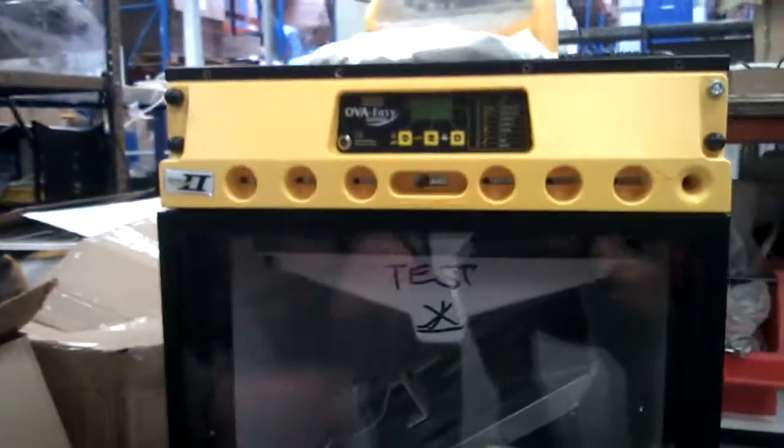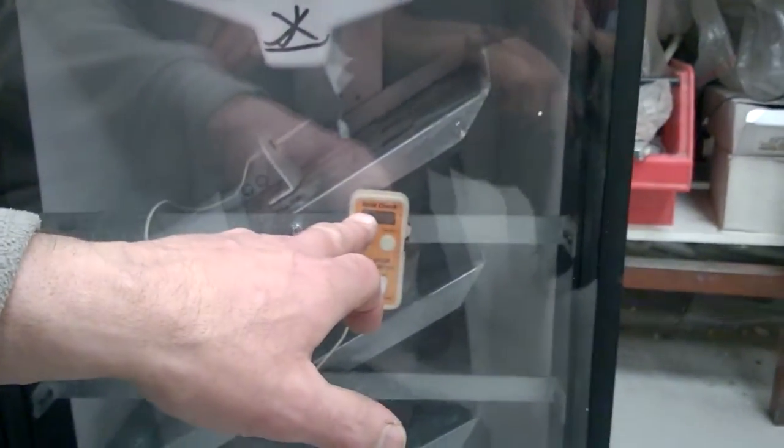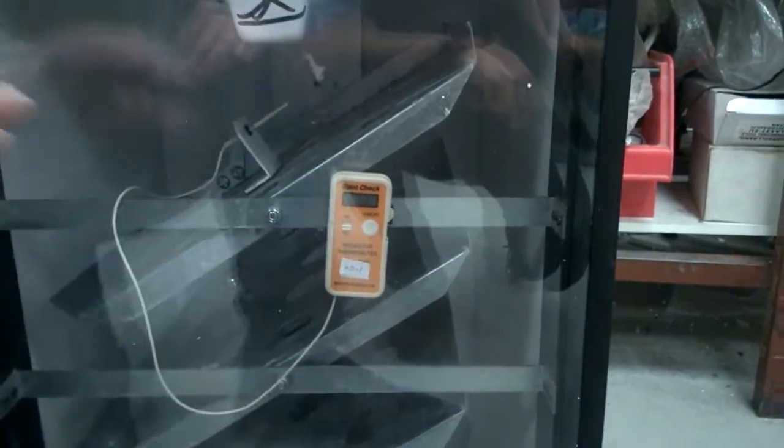The thermometer has been in there for about a good three hours, just to warm through. The thermometer says 37.2. So that's the temperature on the top tray.